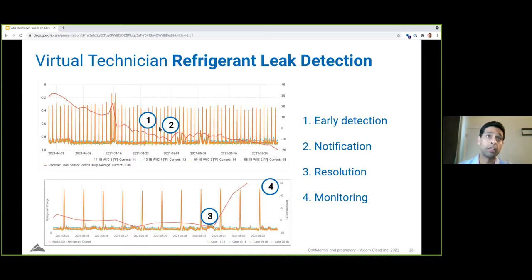So we detected the leak early. As soon as that leak was detected, a notification was sent to the store manager and the service provider. That notification included the estimated impact, the root cause analysis, and links to the relevant data. In this case, because we can't remotely solve a leak, a tech was sent to site to fix the leak and also replenish the refrigerant before an unplanned outage. So in one step, we stopped the leak from happening and also made sure there wasn't an unplanned outage, which could have resulted in food spoilage. Virtual technician will continue to monitor the system afterward to make sure the root cause of the issue is resolved.